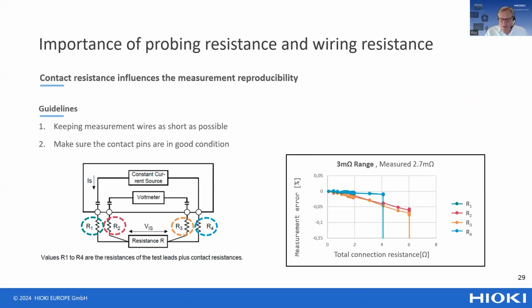Before we focus on the probing itself, I would like to mention the relationship between the total resistance of the test circuit and the measurement error. The total connection resistance, as I mentioned before, consists of the wiring resistance and the probing resistance, and that's for all 4 of the connections that we have with a 4-wire measurement method. On the right-hand side, in this graph, it becomes obvious that the longer the wires are, and the higher the resistance of the measuring circuit is, the poorer the measurement result will be. So the message basically is that you should always try to shorten your connection between the battery tester and the battery as much as possible.